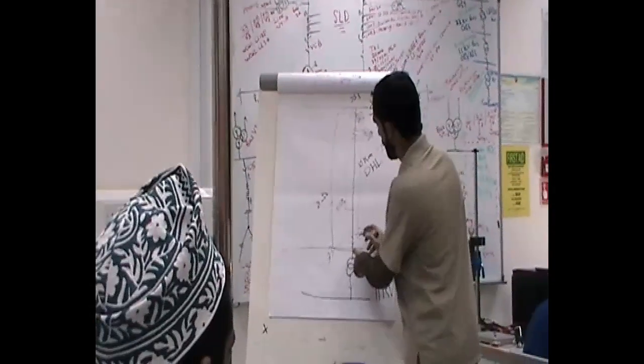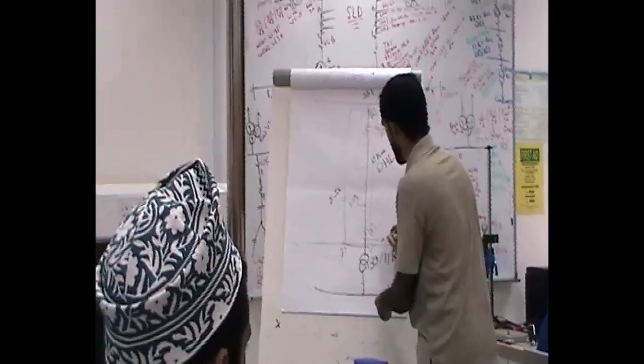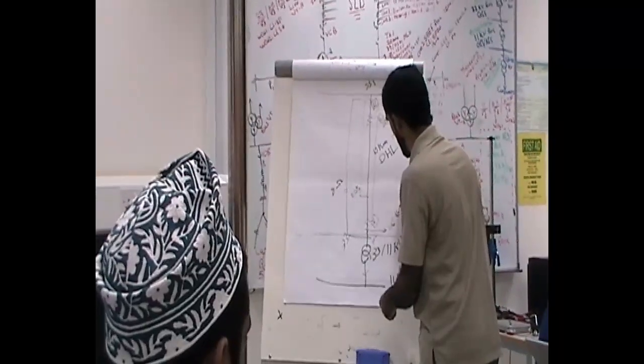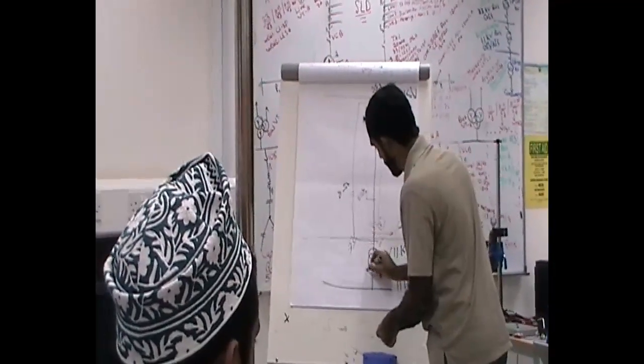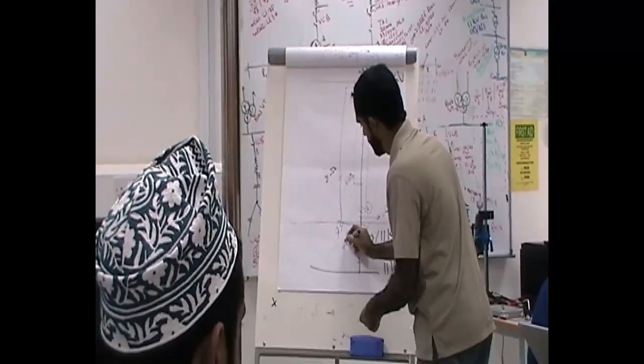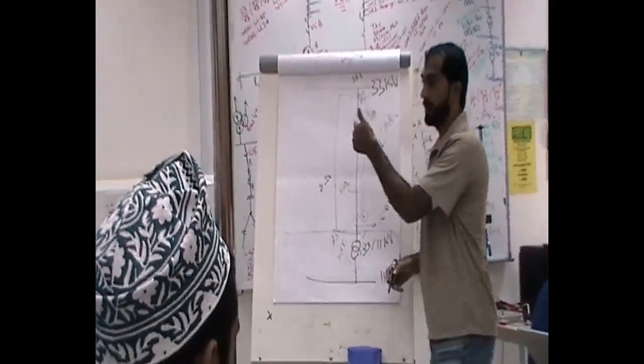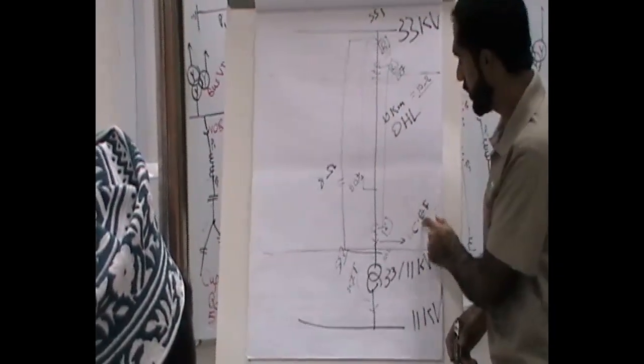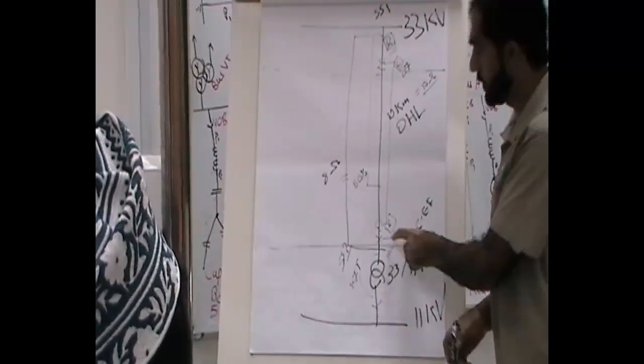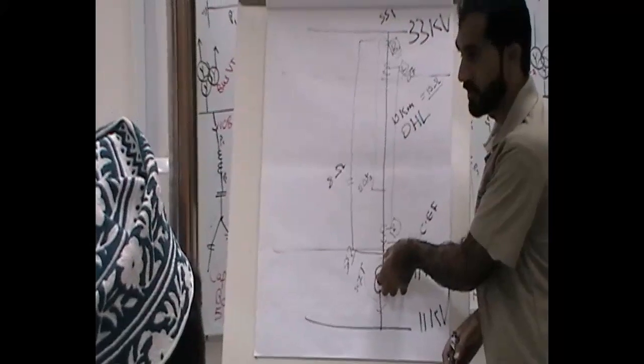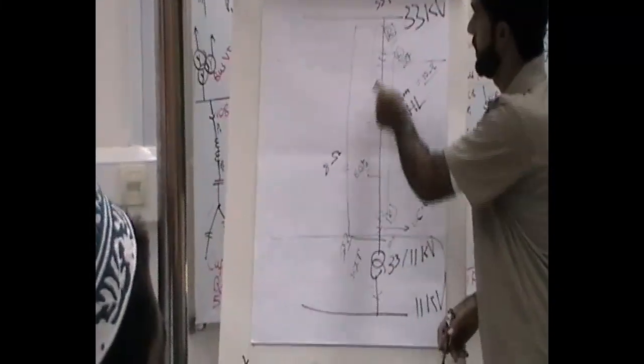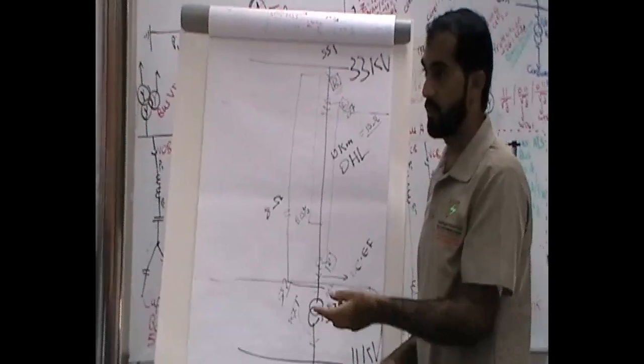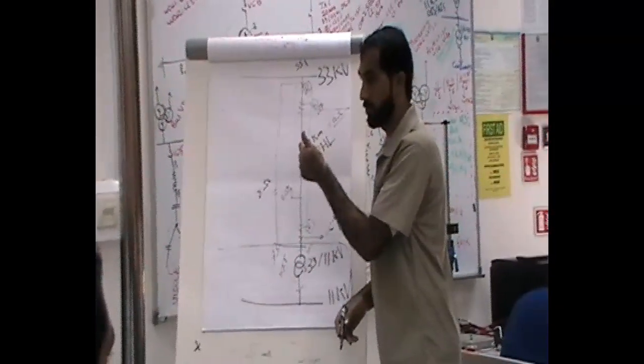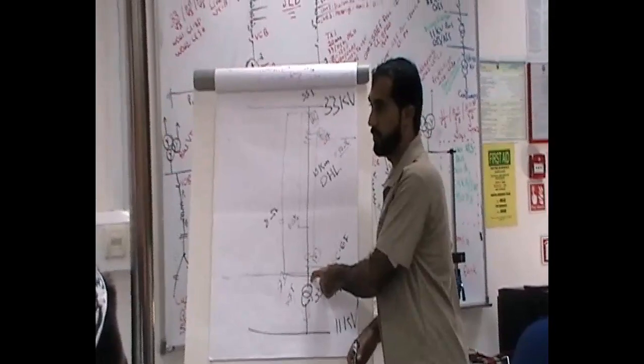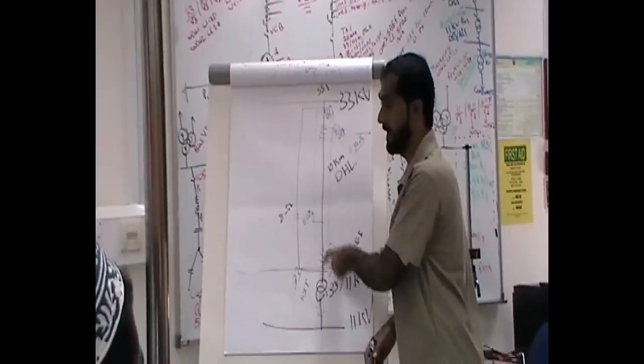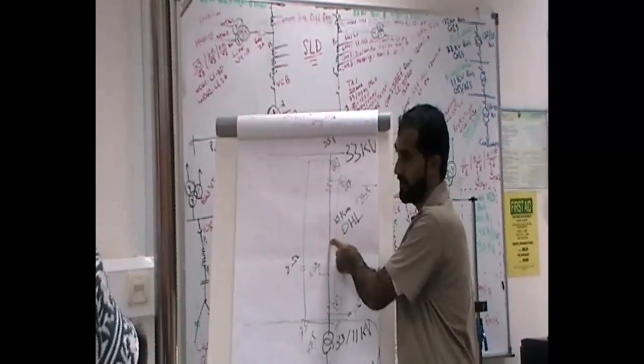Now, zone 2, usually I have here some protection, which is basically overcurrent earth fault. And I have transformer unit protection, 87T. I've given zone 2 400 milliseconds to wait for this overcurrent relay. This should trip if the fault is here at this point. If they didn't trip, then zone 2 will trip. And the engineer, once he's searching if it is tripped in zone 2, he should start from here, assuming that the fault probably will be at this area. Because if it is here, zone 1 will operate.